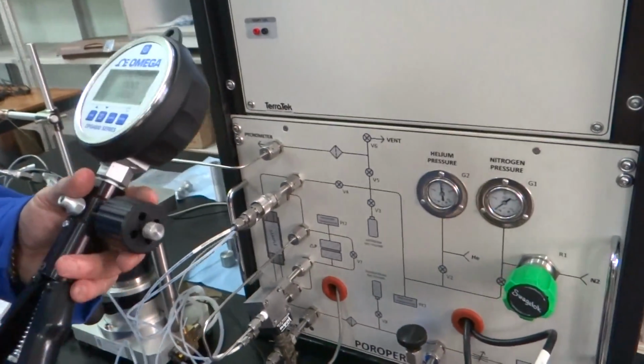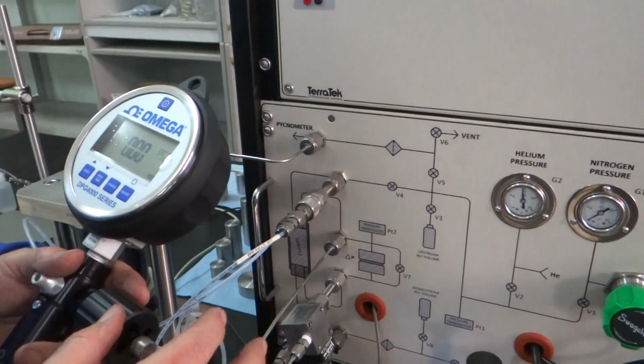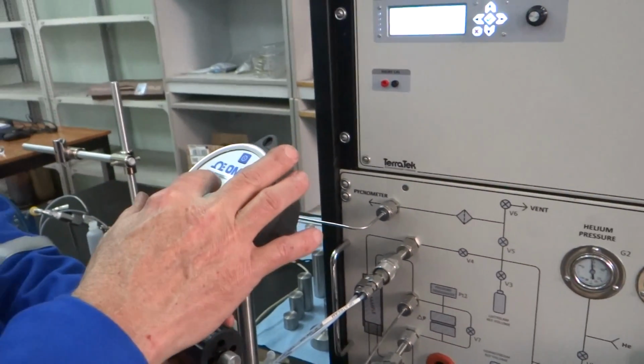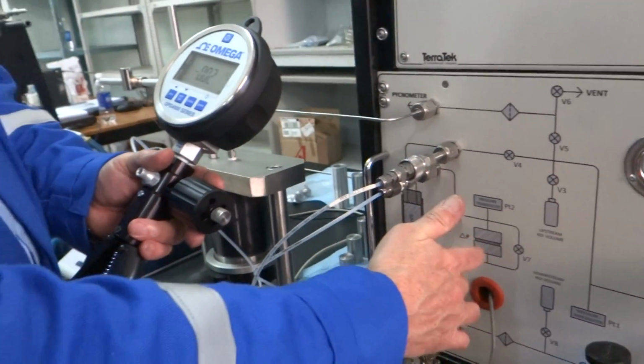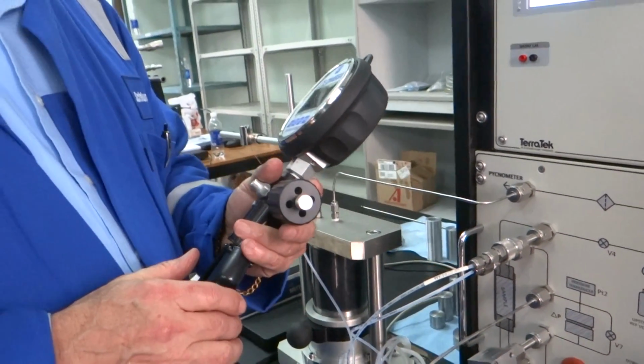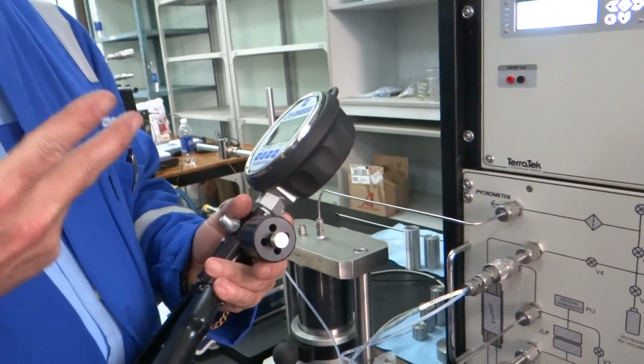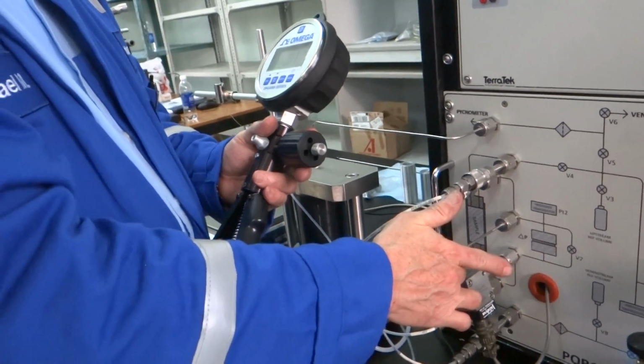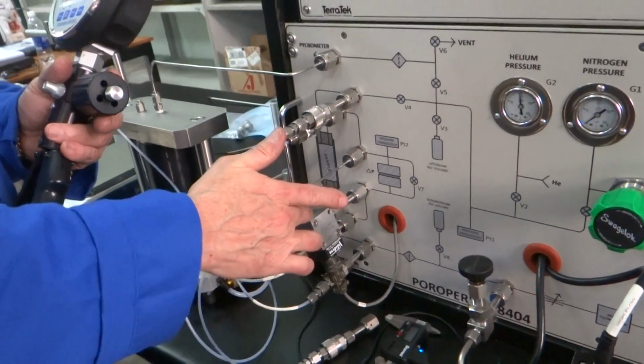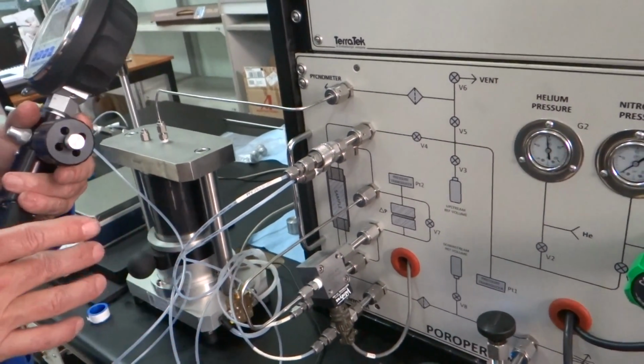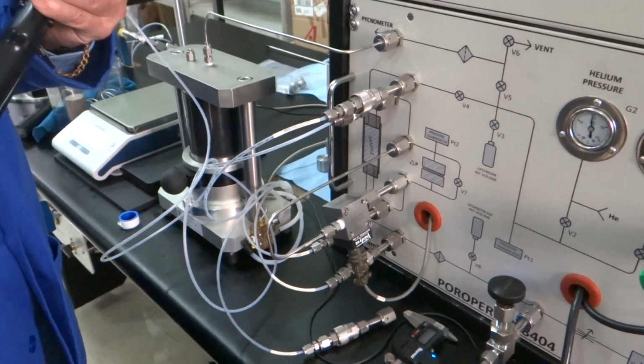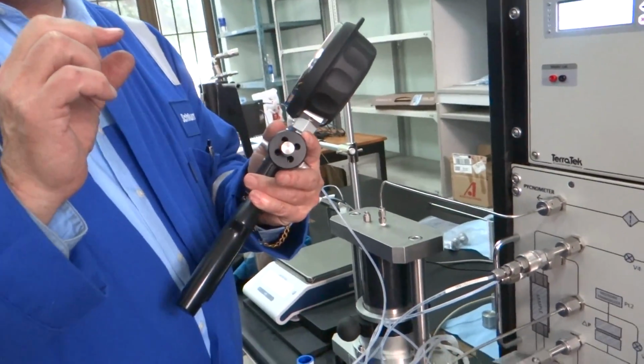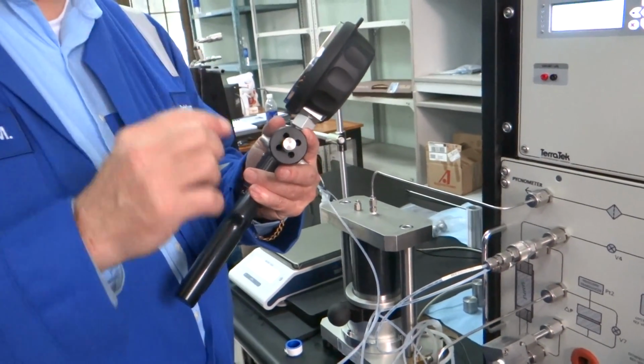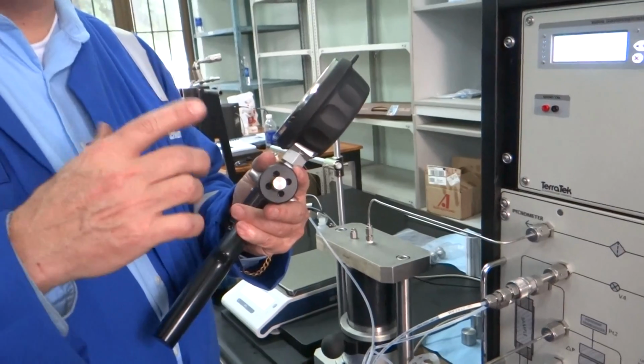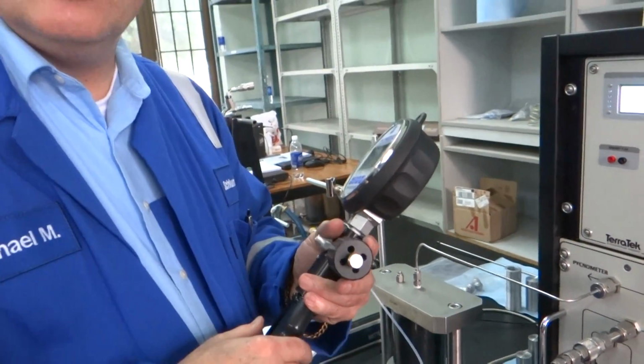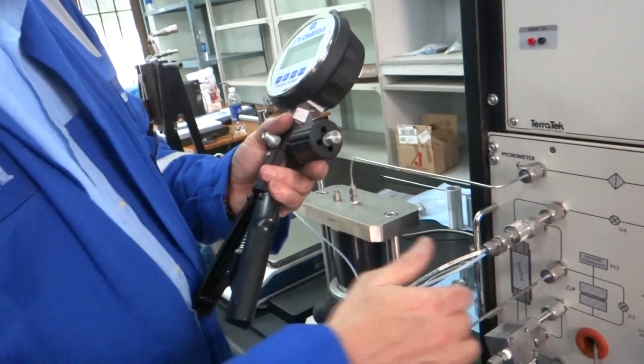So to first set the gain, we'll pump it up to 200 psi, because that's what this diaphragm is. This is a 200 psi. We have 4 diaphragms. We have a 200, a 50, a 20, and a 10. So if the rock is really tight, you have to go down to a smaller differential pressure sensor to get more accurate readings. Yes, of course. I always start with the 200.